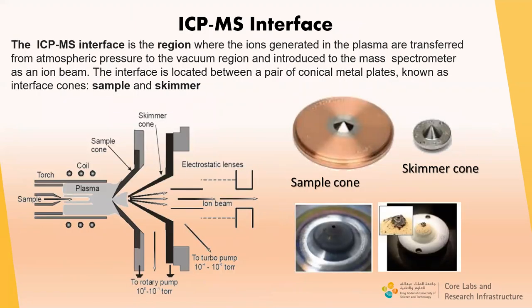The ICP-MS interface is the region where ions generated in the plasma are transferred from atmospheric pressure to the vacuum region and introduced to the mass spectrometer as an ion beam. The interface is located between a pair of conical metal plates known as interface cones — the sampler and skimmer. These cones are responsible for the intensity and stability of the analytical signal. If there are damages to the cone holes or a buildup of deposits on the cones, the intensity and stability of the signal will decrease, and it is necessary to clean or replace the cones.